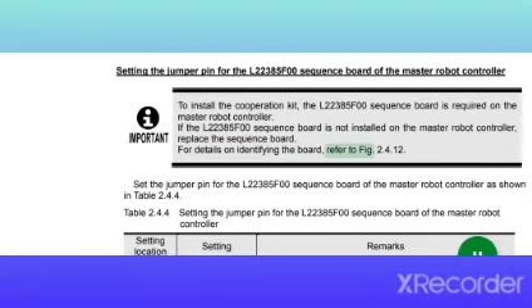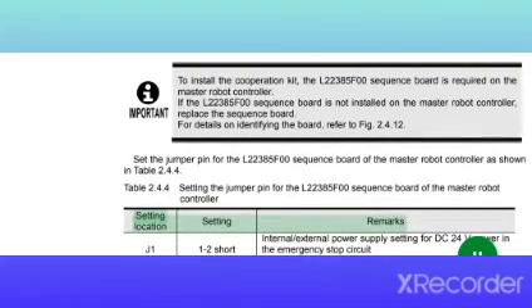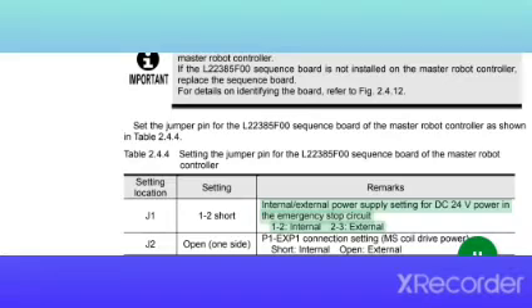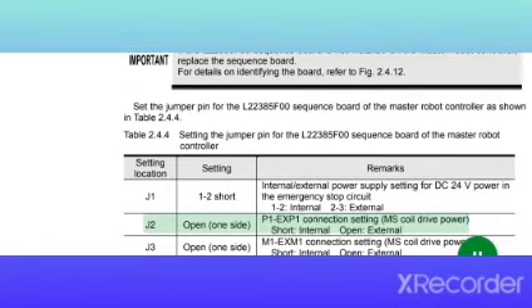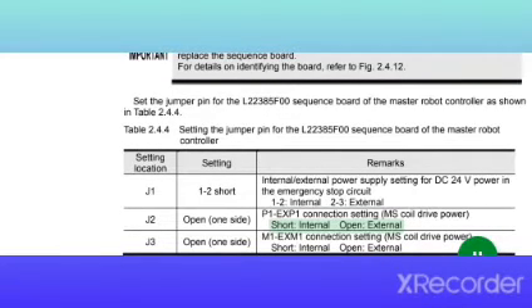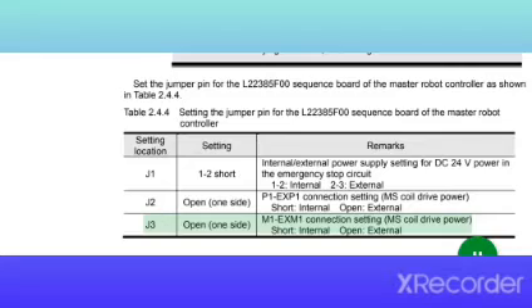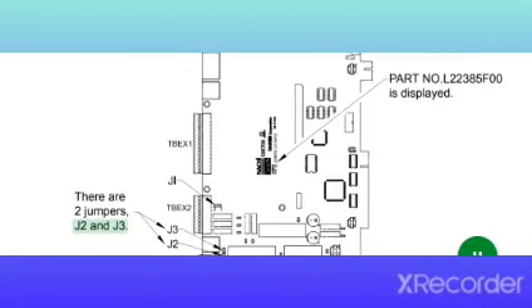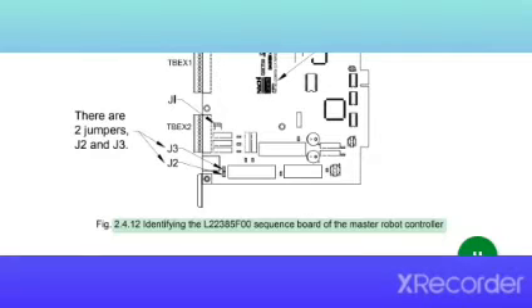For details on identifying the board, refer to Fig. 2.4.12. Set the jumper pin for the L22385F00 sequence board of the master robot controller as shown in Table 2.4.4. Setting location, setting remarks. J1: 1 to 2 short. Internal/external power supply setting for DC 24 V power in the emergency stop circuit: 1 to 2 internal, 2 to 3 external. J2: open one side, P1-EXP1 connection setting, MS coil drive power, short internal, open external. J3: open one side, M1-EXM1 connection setting, MS coil drive power, short internal, open external. There are 2 jumpers, J2 and J3. Part number L22385F00 is displayed. Fig. 2.4.12 Identifying the L22385F00 sequence board of the master robot controller.